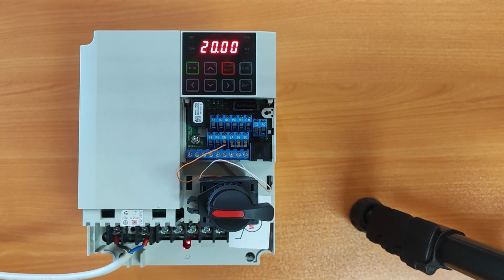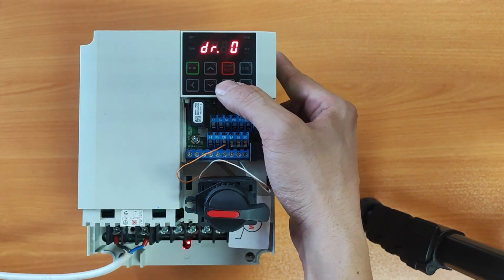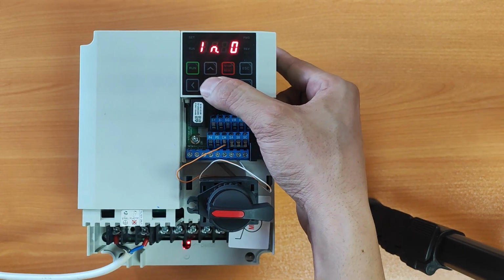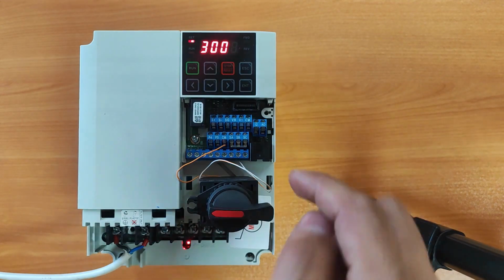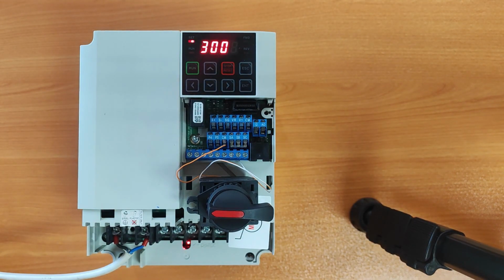All right, as we said, if we want to set up on delay and off delay for the digital inputs on this inverter, we need to enter the parameter group for this. In parameter 85, we have to set the delay for the digital input to turn on. Set the time, and in parameter 86, we can apply the delay for turning off. All right, now I've entered parameter 85 and I'm setting its value to 3,000 milliseconds or 3 seconds, which means that if I activate the digital input, which I've connected here, it will activate after 3 seconds and this will start the inverter.